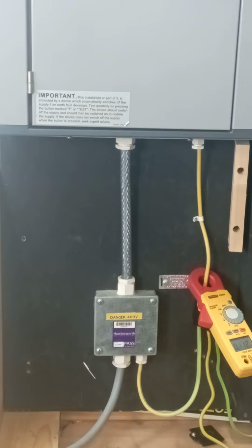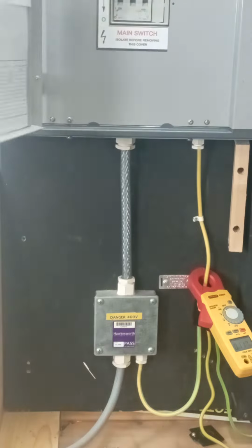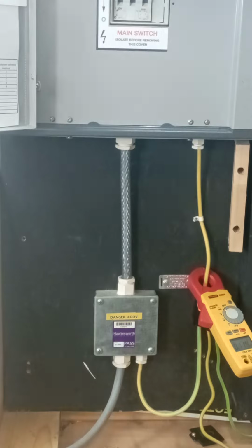Okay, so it's dropped down to 0.1 of a milliamp. As I start to isolate the rest of the installation, we probably shouldn't see much of a change in it. Still around about 0.1 milliamps. This is current that's just circulating within our earthing arrangements within the installation external to this point. This is a standalone static board and there are no other parallel paths introduced.